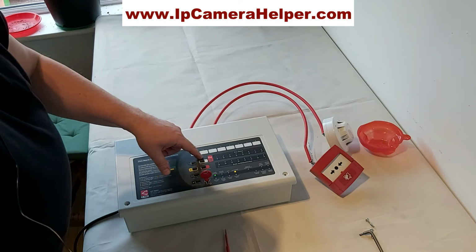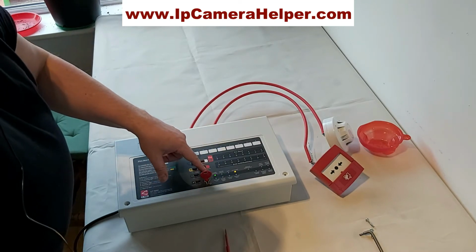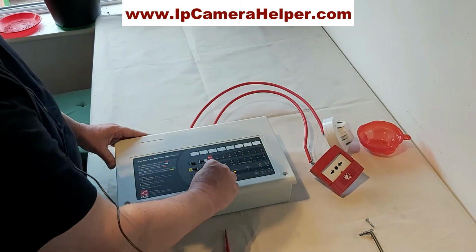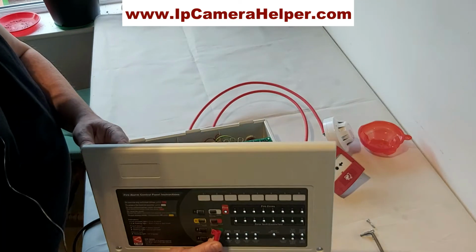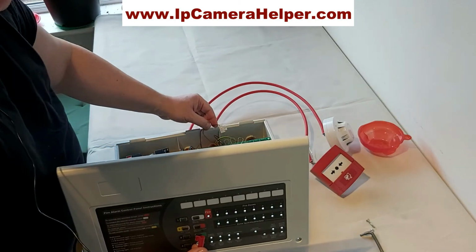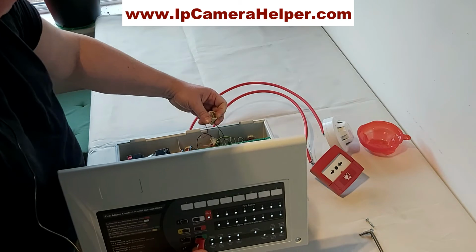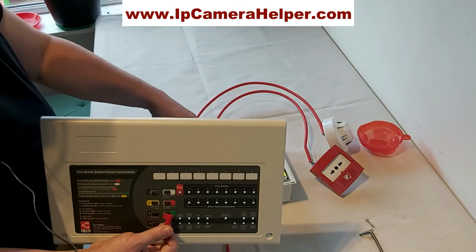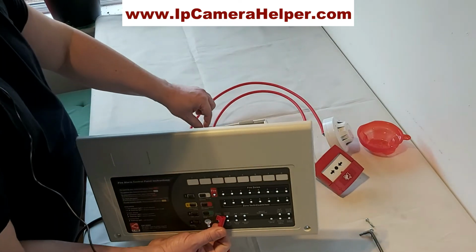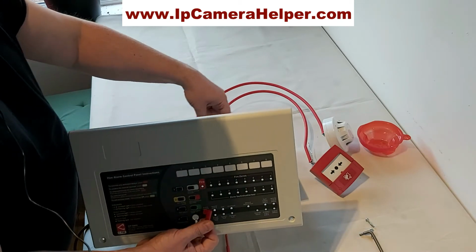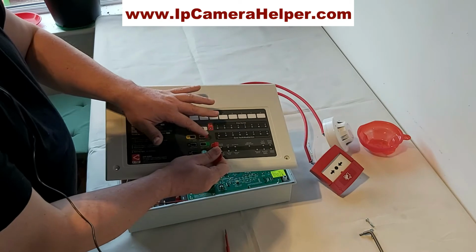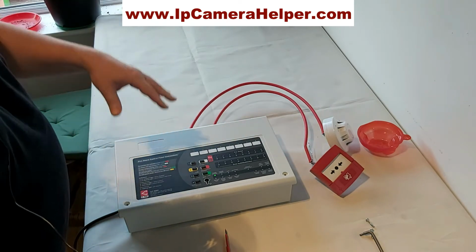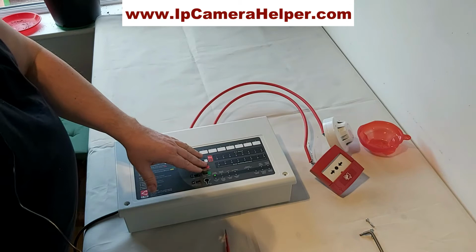So the white one here is silencing internal sounders. The red one is silencing external sounders. I don't have real external sounders connected, because they make a lot of noise. But I have connected a pseudo siren like that. It's not making that much noise, but still it will be making additional noise except beeping in the panel. So this is my external sounder. It will go off when the alarm goes off, and it will silence when I press silence sounders. These are external sounders or beacons, because they could also be visual. You silence them with that.